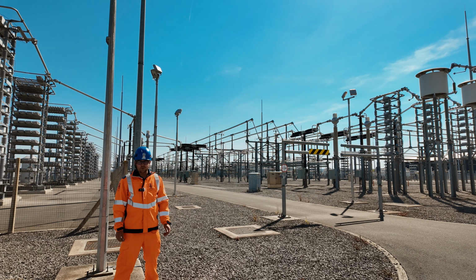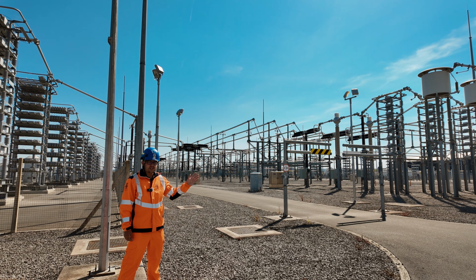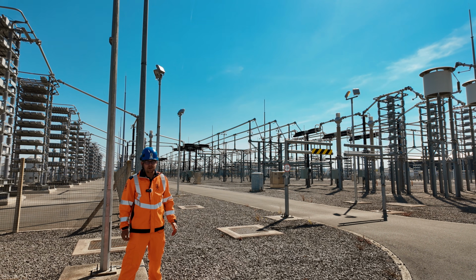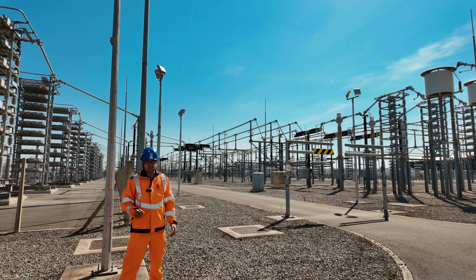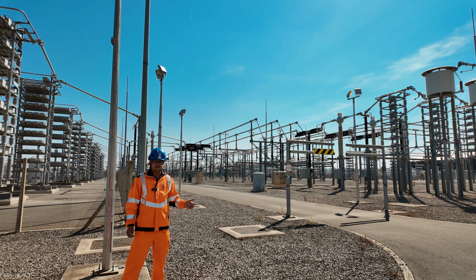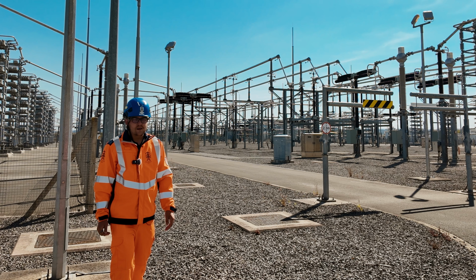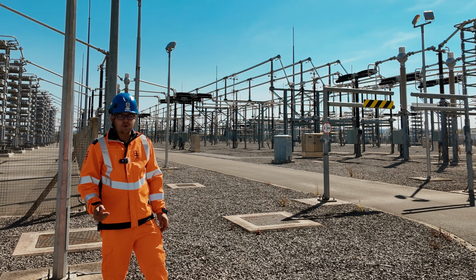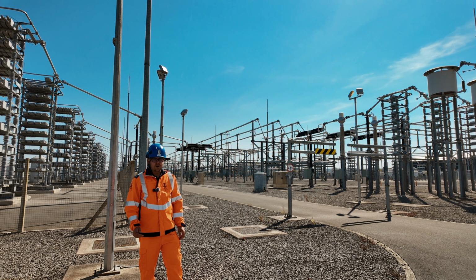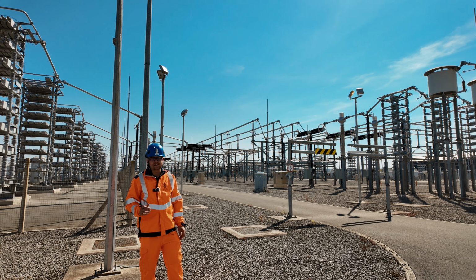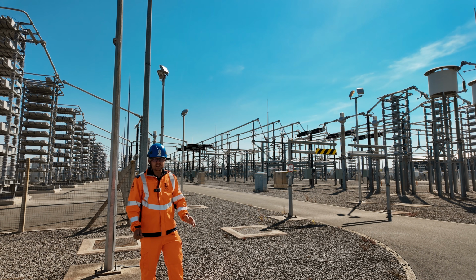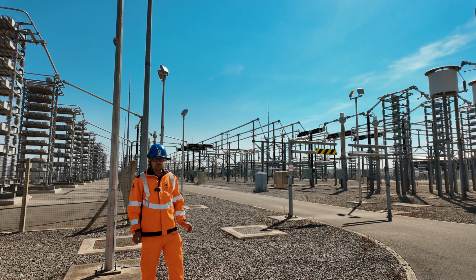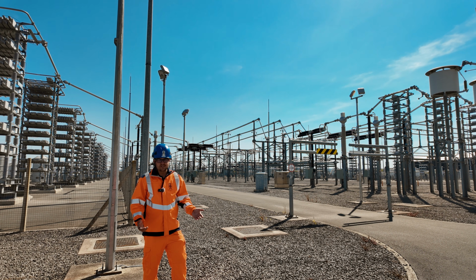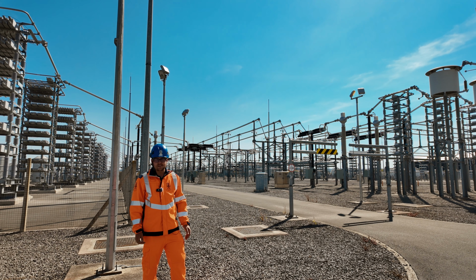In this case, power is flowing down our bus bars out of our converter station here, which is like a big switching power supply, working in reverse and producing some dirty power, with let's say 5th and 7th harmonics to keep things simple. In this filter we have that resistor I mentioned before, and its job is damping. Our capacitor and reactor are going to create a resonance circuit which is really good at attracting particular harmonic frequencies, but we don't necessarily want that resonance to be incredibly sharp. The resistor adds resistance to the circuit, controlling that resonance and dissipating some of that harmonic energy as heat.